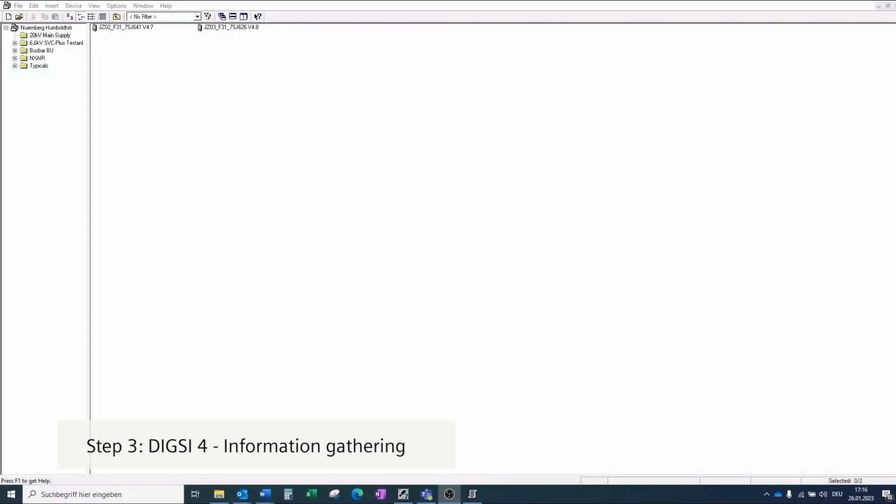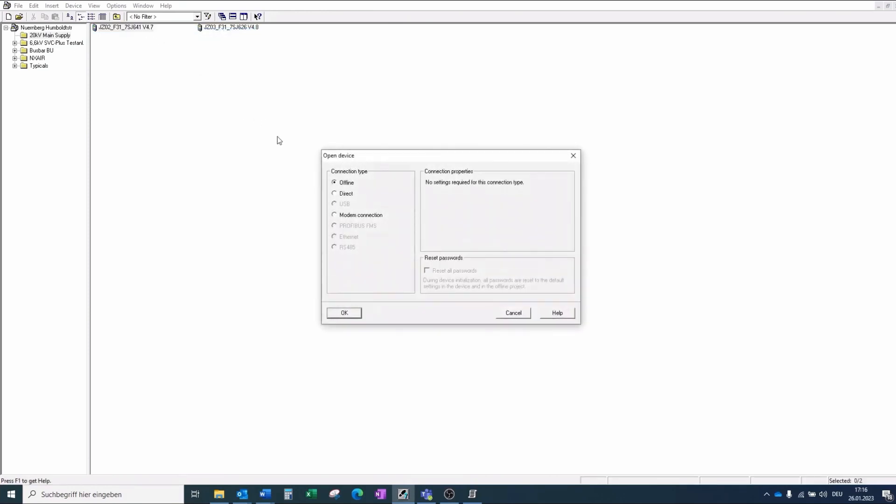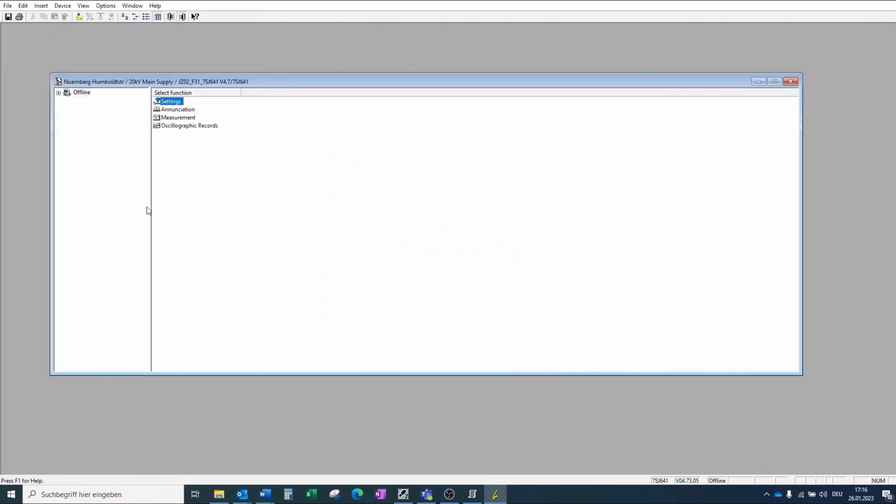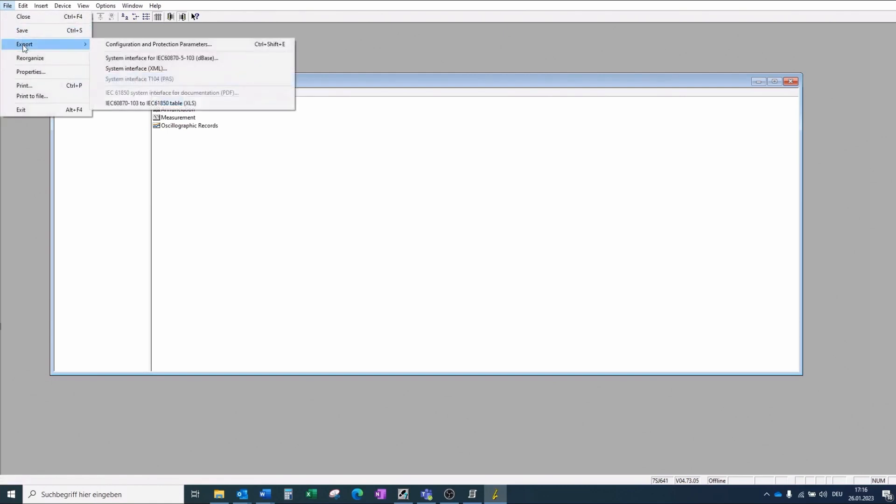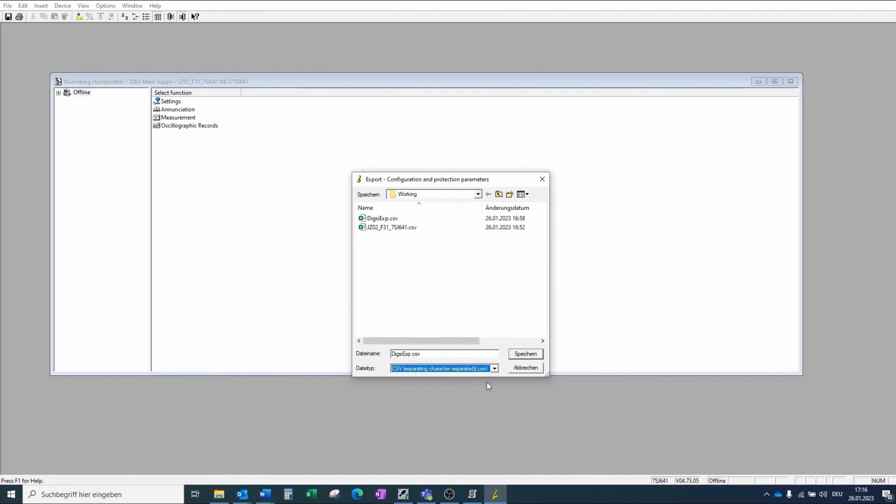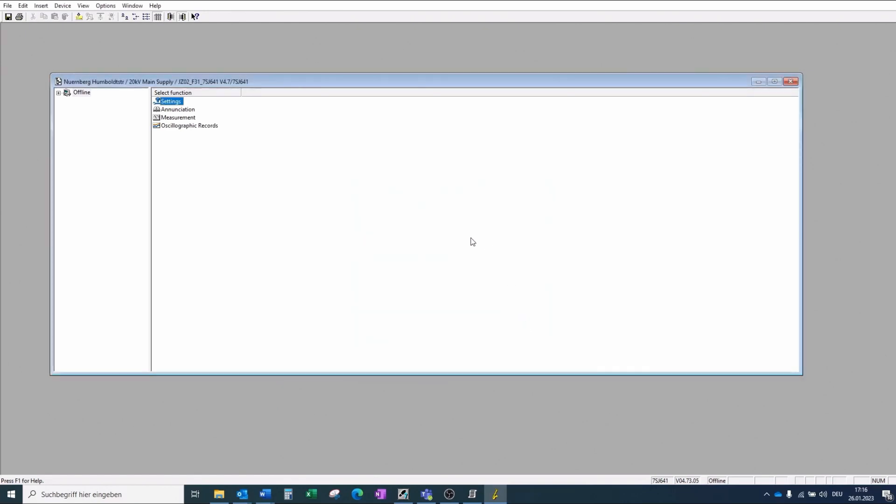In the next step, we will prepare the configuration information of the 7SJ641. To do this, we open the device with OpenProject and then we export and select configuration and protection parameters. Then we select CSV file and store it. As a result, we get a corresponding CSV file.